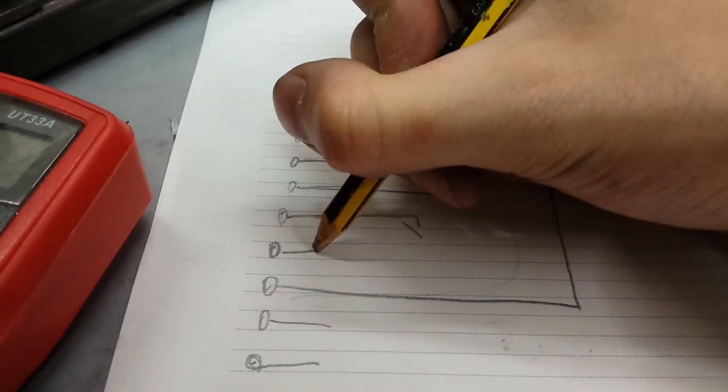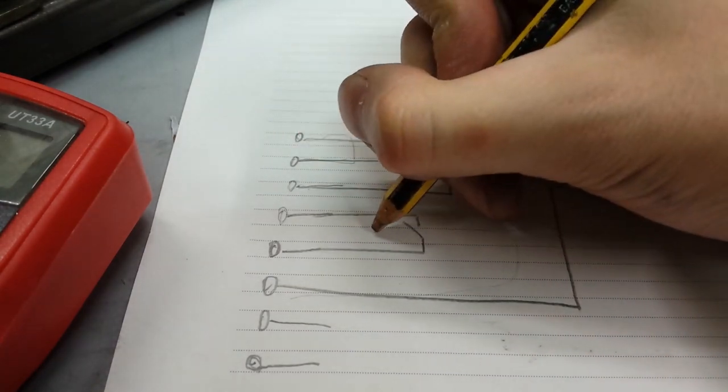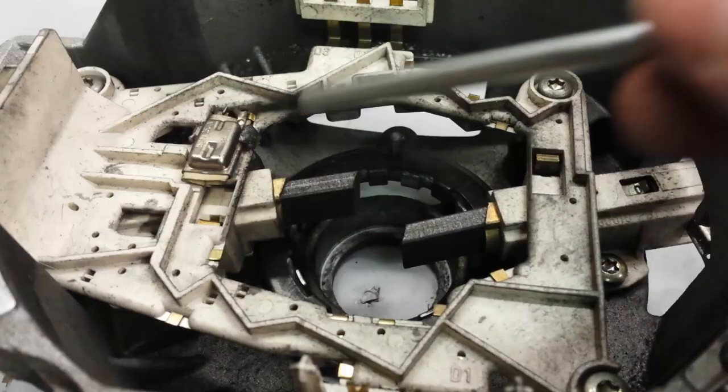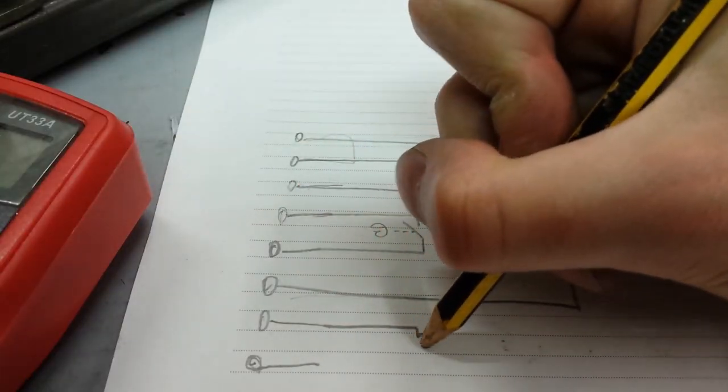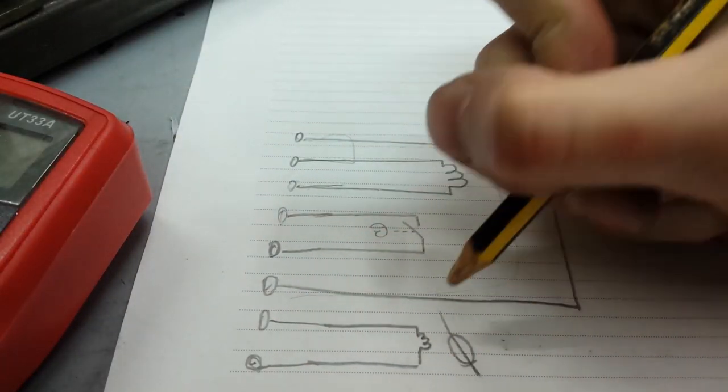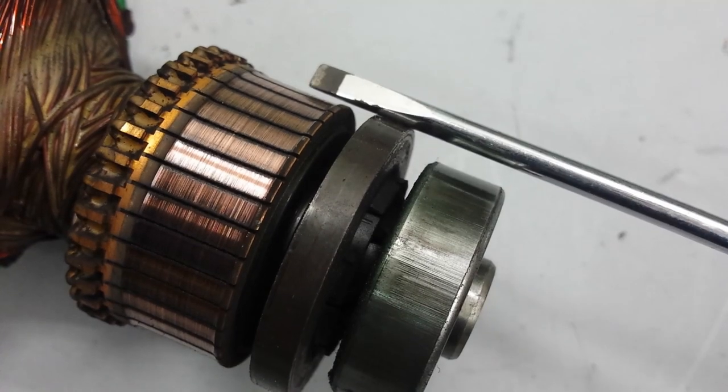The optional ones can be two for a safety element which is a thermal switch that opens as soon as the motor heats up. Lastly, two for the RPM sensor which is a coil with a magnet mounted on the rotor.